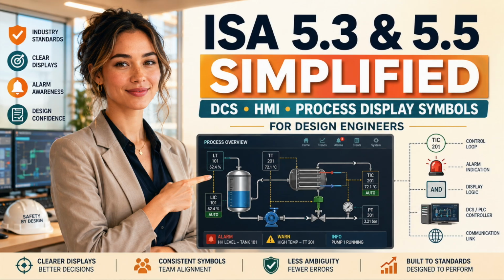The symbol library itself must be governed as an engineered asset. Every reusable object should have a controlled identity, defined geometry, connection points, dynamic states, alarm behavior, failure behavior, interaction rules, and version history. A pump object should not be copied from another unit, detached from the approved library, and modified because one screen designer prefers a different color or animation. A change to a standard valve object may affect hundreds of displays. A change to state logic may alter operator interpretation across the plant. These are controlled engineering changes, not casual graphic edits.